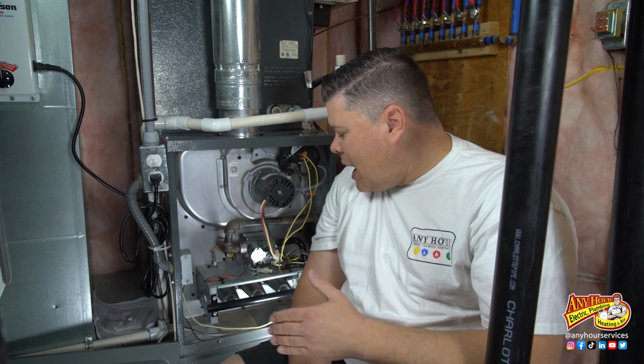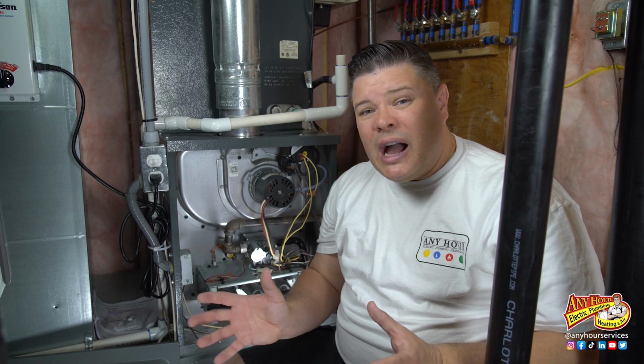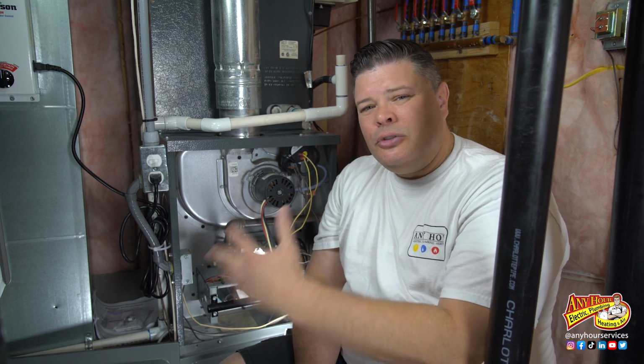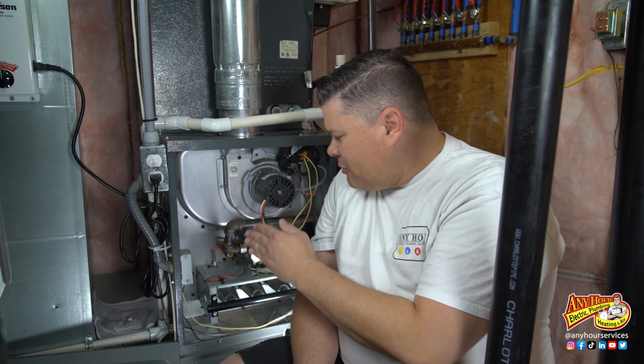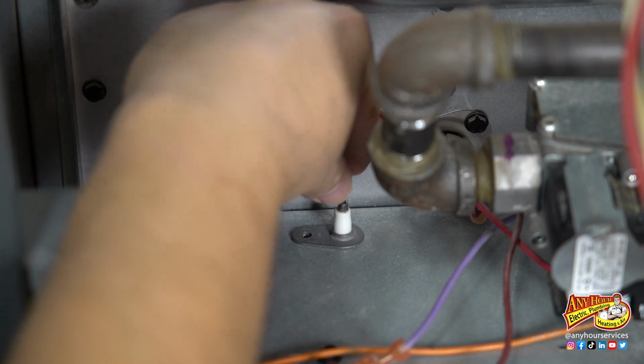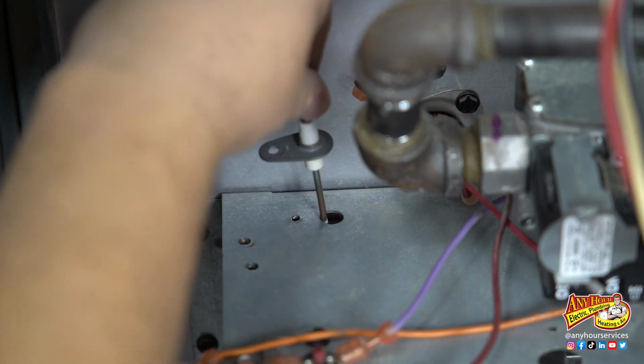Most furnaces are going to try and go through that ignition sequence several times before it goes into what's called a lockout mode, where it won't try that ignition anymore, and then it'll come out of that and it'll try some more times. But whenever the flame sensor is not detecting a flame, the most common reason for that is carbon buildup on the flame rod itself.